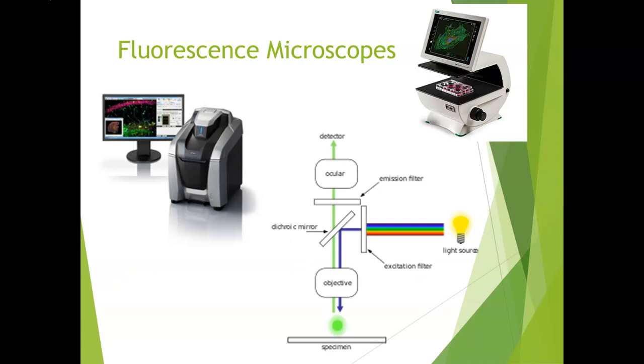Fluorescent microscopes are often used in cell culture facilities. Fluorophores — the fluorescent molecules — are used as markers for cell structures and emit different colors of light. The microscope must be set up with the correct filters in order to visualize the emissions. The light source passes through a filter which allows the excitation wavelength of light to continue on and interact with the fluorophores on the specimen. The fluorophore absorbs one wavelength and emits another — this is the definition of fluorescence. The emitted wavelength passes through yet another filter, the light signal is often amplified, and then enters the oculars. In the modern setup, it is displayed on a computer screen so that images can be captured.